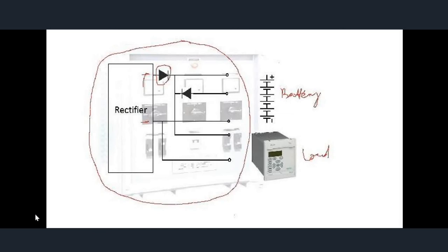There are two modes of charging in the rectifier: first the float mode and the boost mode. If the nominal voltage of the battery is 110 volts, then in float mode the output voltage of the charger is around 120 volts. So the charging of the battery in float mode will be above 110 volts and up to a maximum of 120 volts. But with boost mode charging, the scenario goes different.